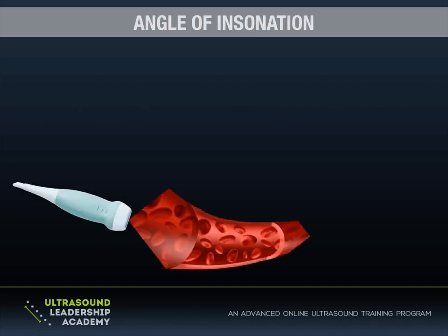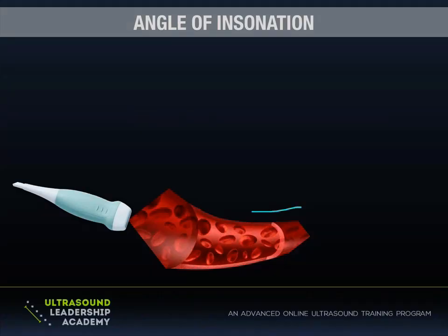And speaking of angle, this is the concept. The concept is that if you have a blood vessel, and let's say that the blood is coming through the vessel this way, flowing through the vessel like that. In order to get the truest representation of the Doppler shift, in order to get the truest representation of what blood flow is doing in that vessel, you'd like to take an ultrasound transducer and place it directly in the vessel, facing either directly towards or directly away from the flow. And that would get you an angle of insonation of either 0 degrees or 180 degrees, which, if we refer back to the Doppler shift equation, is going to get us the highest degree of Doppler shift.